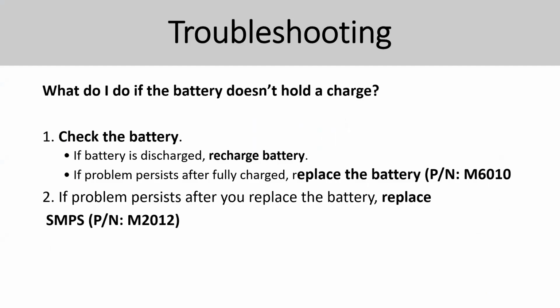Troubleshooting. When you talk about patient monitor troubleshooting, the first thing is that the battery is a very common problem. So you need to discharge the battery and recharge the battery and check if the battery works properly or not. If it is not working, you need to replace it. Normally you need to know the part number of the battery and the part number of the replacement board as well. If the battery is working properly, but the charging circuit is not working when you exchange the battery to another patient monitor, that means you need to replace the charging board as well.